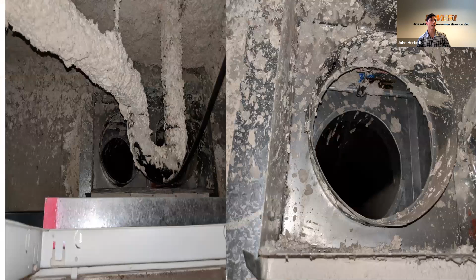I'll get to my first project. This was at an existing hospital here in the Portland area, and what they were trying to do on one of these projects is reduce the amount of FSDs and fire dampers they had in the field. So they have to get a fire protection engineer and someone familiar with the building to really go through all the smoke compartments and fire compartments and start taking a look at where they can start reducing that to meet current code.